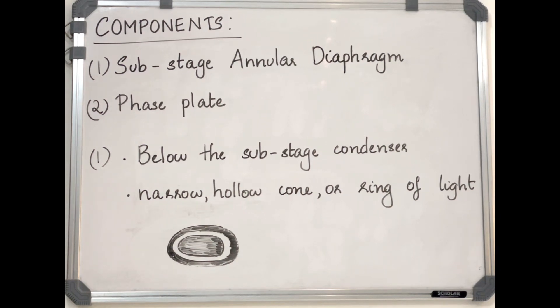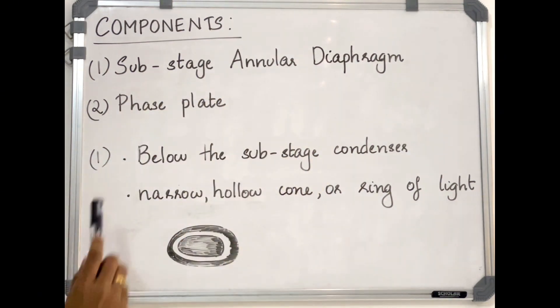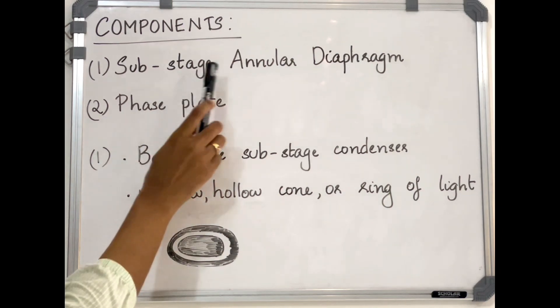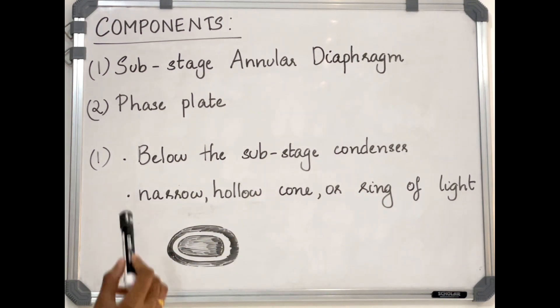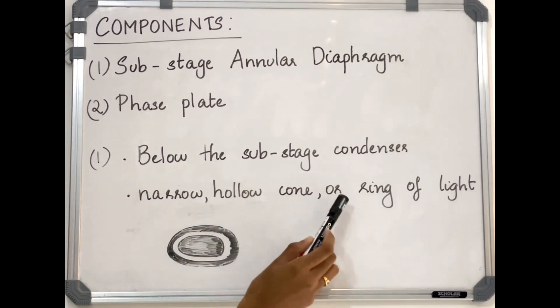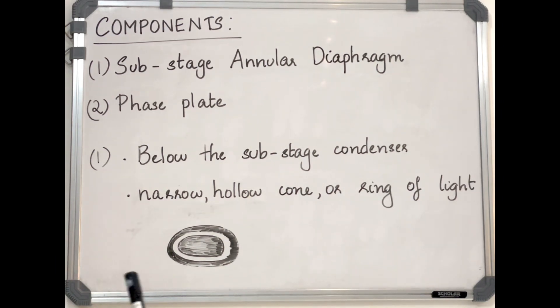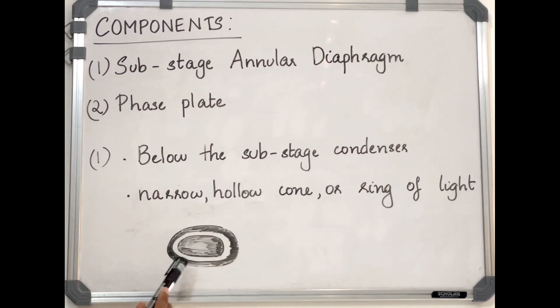Components of the phase contrast microscope: it is similar to an ordinary compound microscope, having a light source, condenser lens, objective lens, and ocular lens. But there are two additional components — the sub-stage annular diaphragm and the phase plate. The sub-stage annular diaphragm, also called the annular ring, is located below the sub-stage condenser and helps create a narrow hollow cone or ring of light.